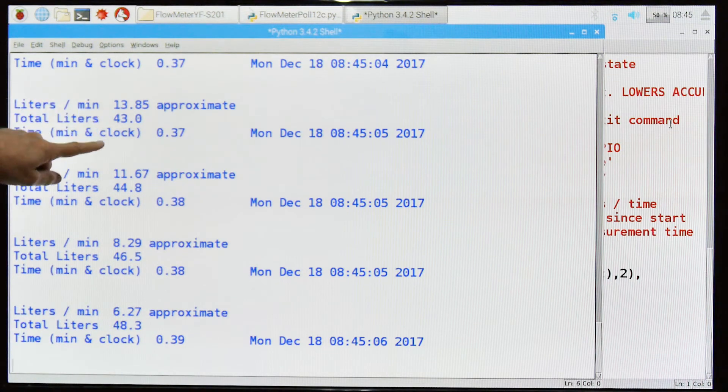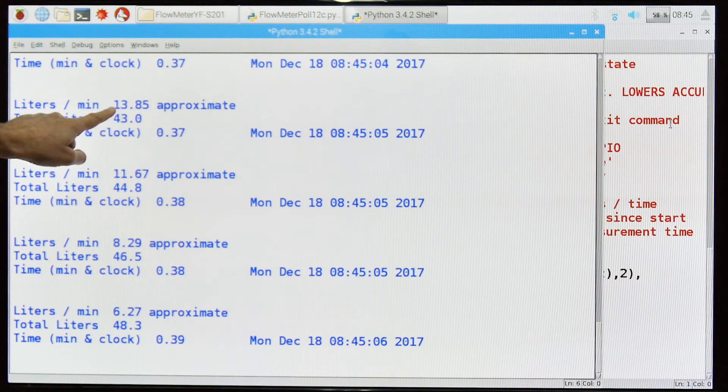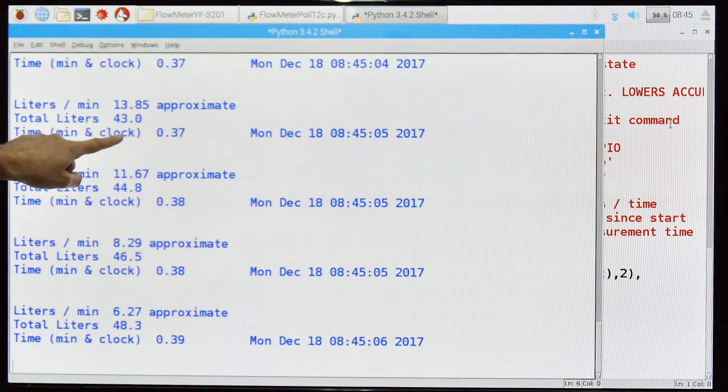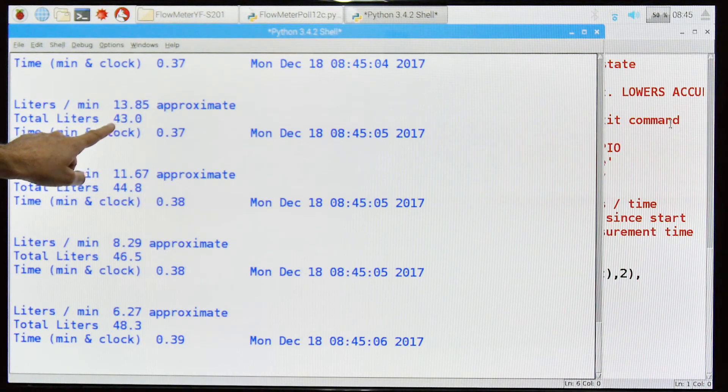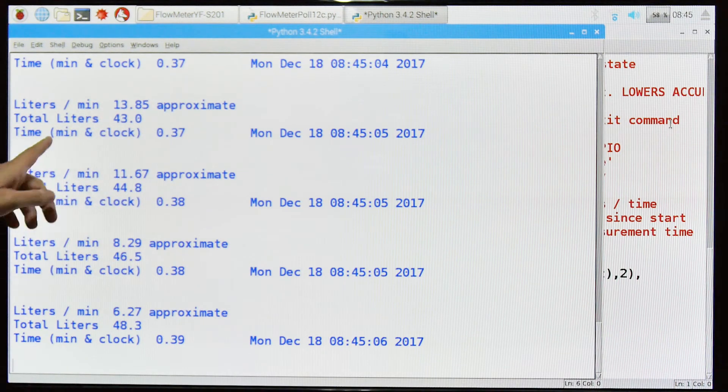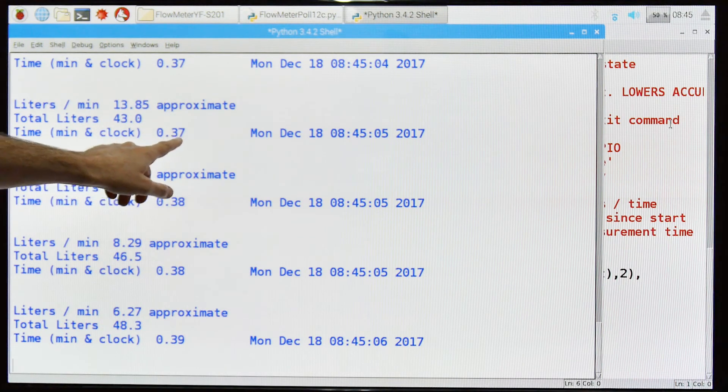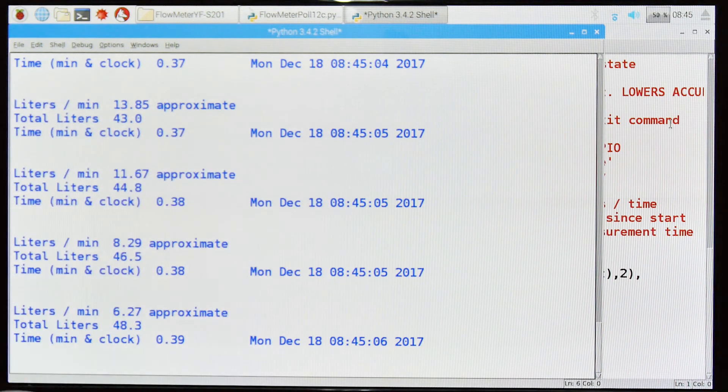You can go back and change that so you get a one minute or whatever you want type interval. But here you can see total liters per minute is 13.85. Now that's a rate, okay. That's based on how fast the impeller is turning, that's not actual, it's an estimated. Total liters would be 43 at the speed I was blowing through there. And the total amount of time that passed was 0.37 and here's the actual wall time.